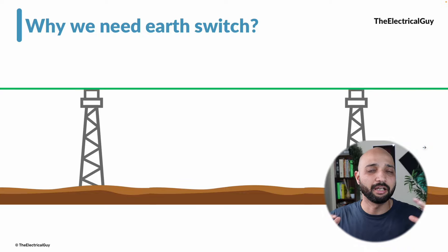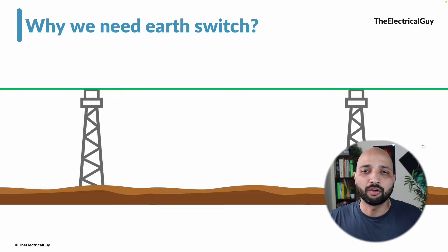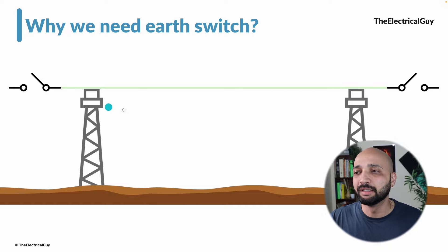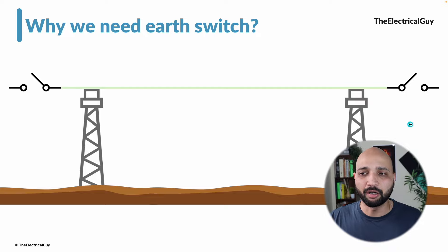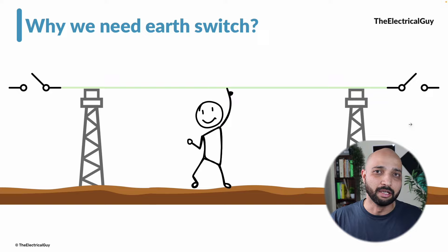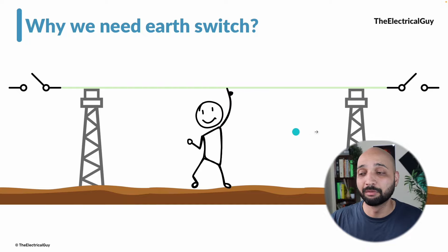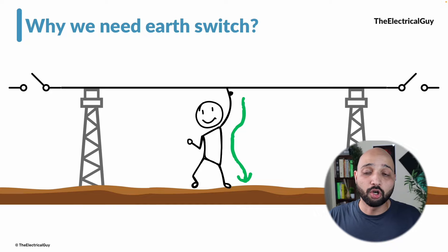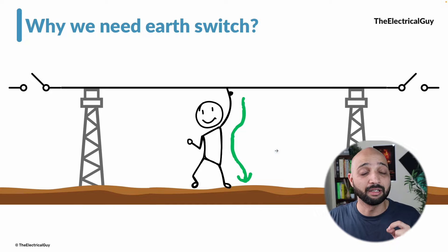A similar scenario happens with electrical power. Imagine a transmission line carrying power over a long distance. If we turn off and disconnect that line from both ends, power stops flowing. But there will still be some charges — free electrons trapped between those sections with no path to go. If an operator touches that line accidentally during maintenance, those trapped charges will find a path to ground through his body, which can be very dangerous and even life-threatening.